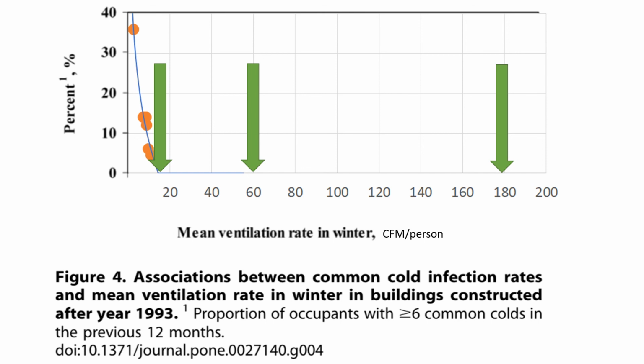And certainly in the healthcare industry, we've taken this out to kind of ridiculous extremes. The minimum ventilation rates that we use ostensibly to combat disease transmission are generally way out beyond any point of diminishing marginal return, and so we've got to be conscious of that. Having a relationship to infectious disease transmission is not an excuse to just blow cost and energy out the window. And so that was what I was thinking.